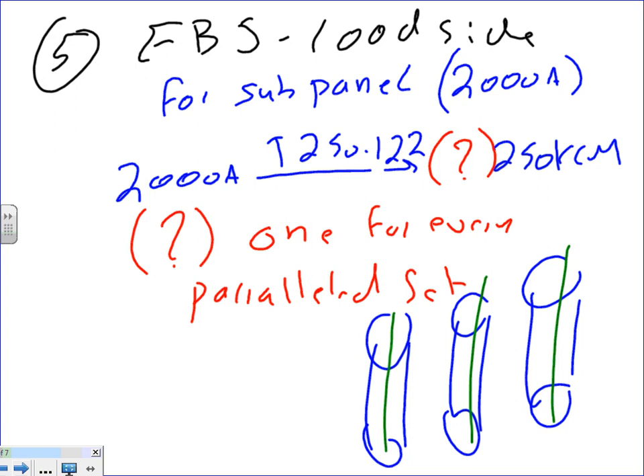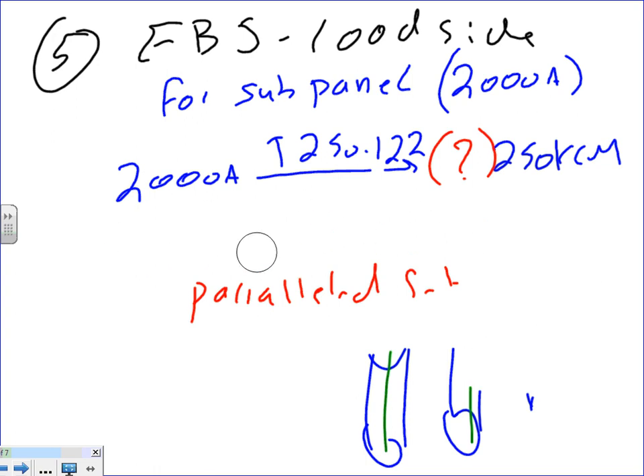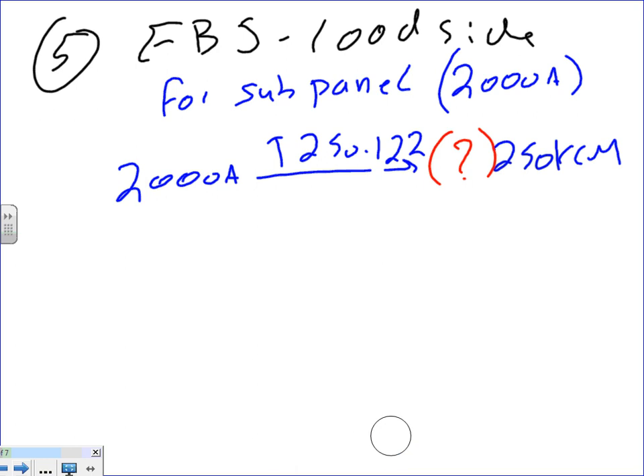Oh, no, Chad. I think I'm doing the equipment ground conductor here. Don't listen to me. This one is basically 1, right? You can see what we're doing. That's what I said. This is going to be only 1. Everybody can see why? Because we're just tying the conduit where it's located right now. If you look at the diagram, it's just tying the conduit to the ground rod. Where number 5 is located, it's just tying the conduit to the ground rod. So it's 1. Number 6 would be right. Any question, guys, about number 5?